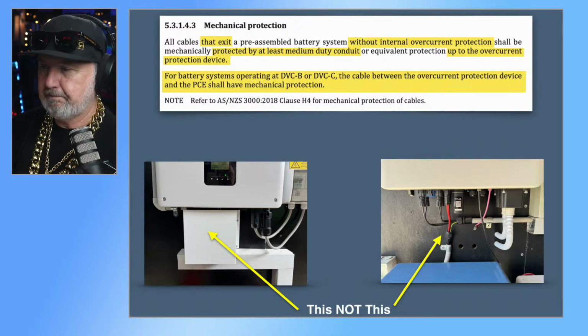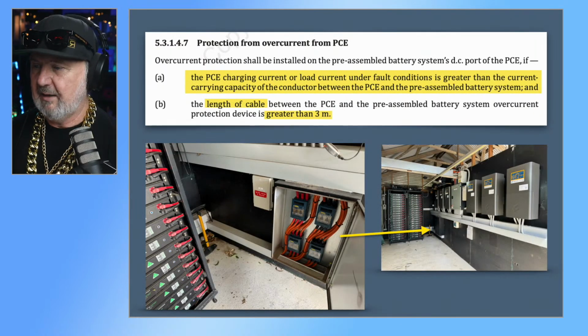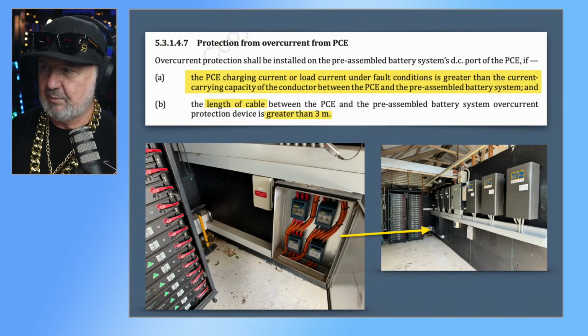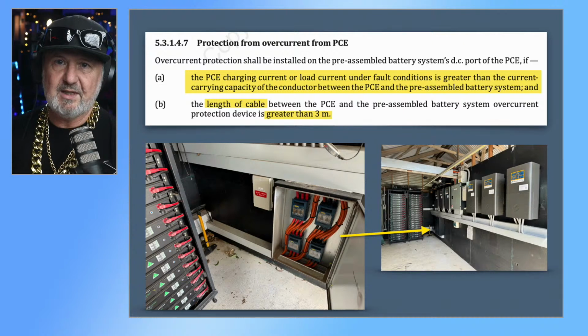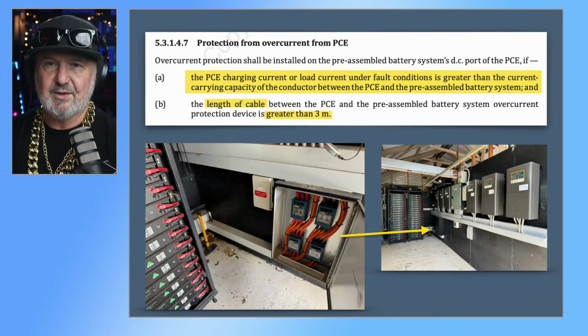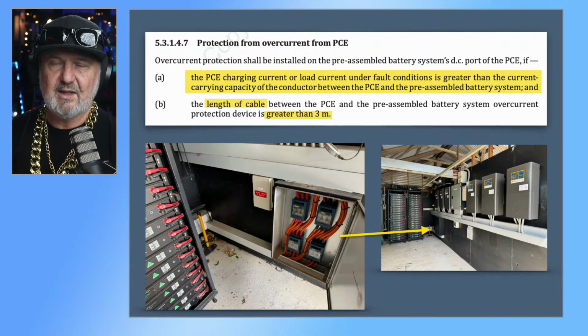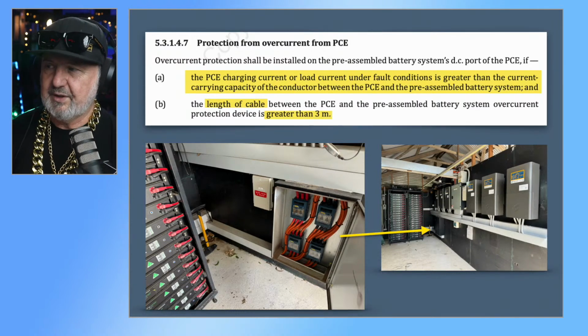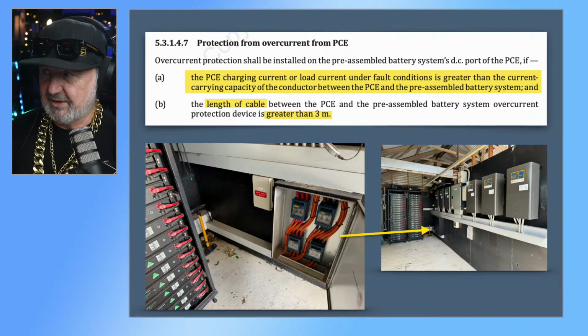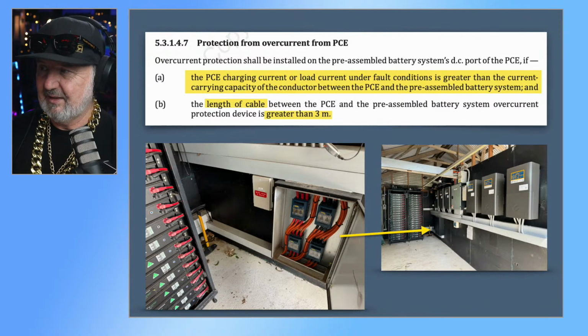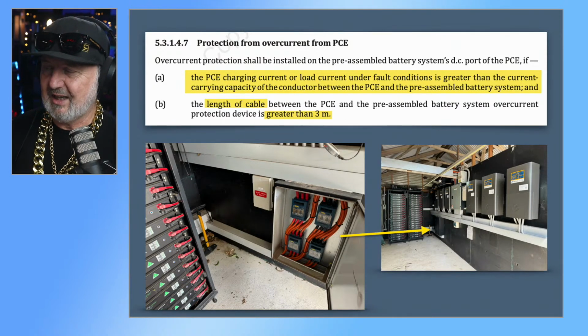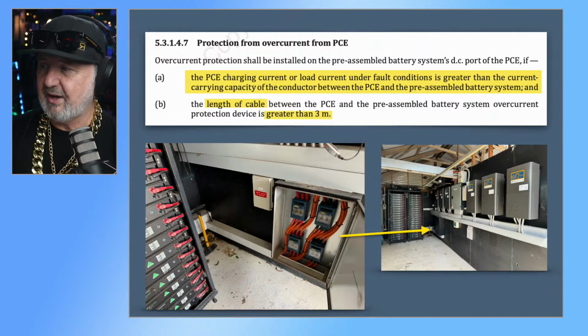Okay, moving on. What are we up to here? So, protection from overcurrent from the PCE. You've got two sources. The batteries can source current into that cable, and the PCE can source current into that cable. And the overcurrent protection shall be installed on the pre-assembled battery system's DC port of the PCE. So at the inverter, this is where you need overcurrent protection at the inverter, if the PCE charging current or load current under fault conditions is greater than the current carrying capacity of the conductor between the PCE and the battery system.